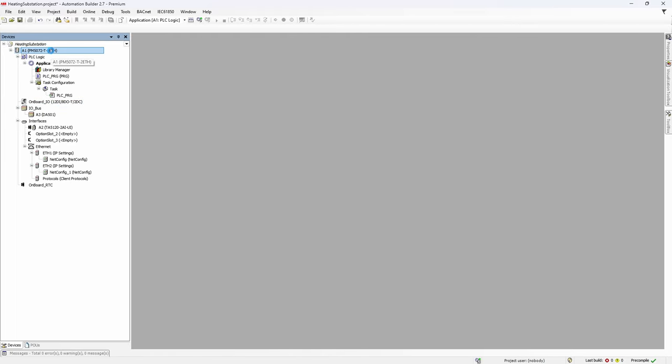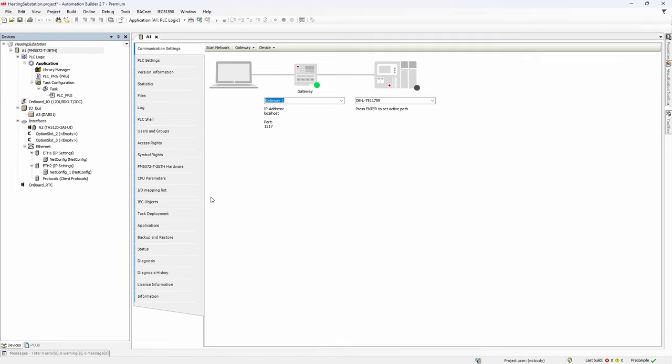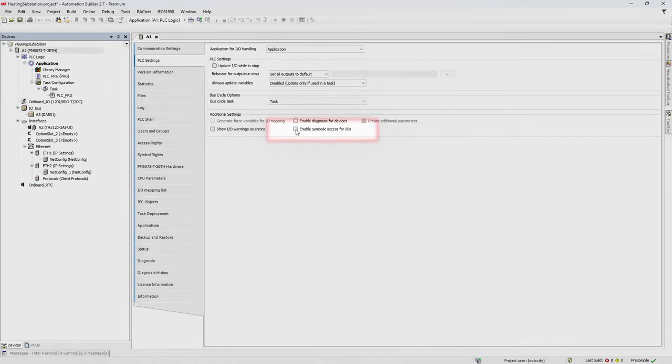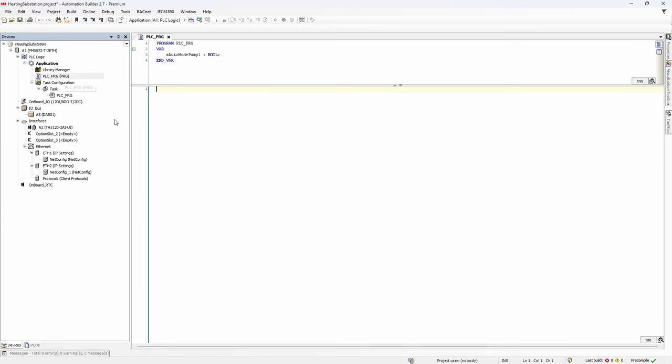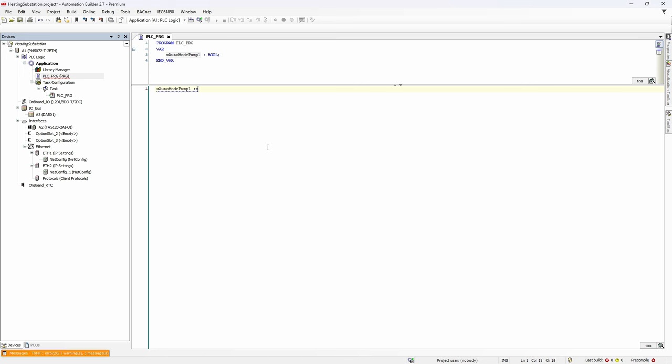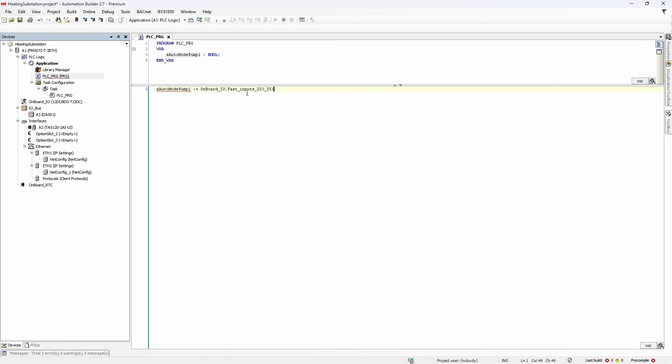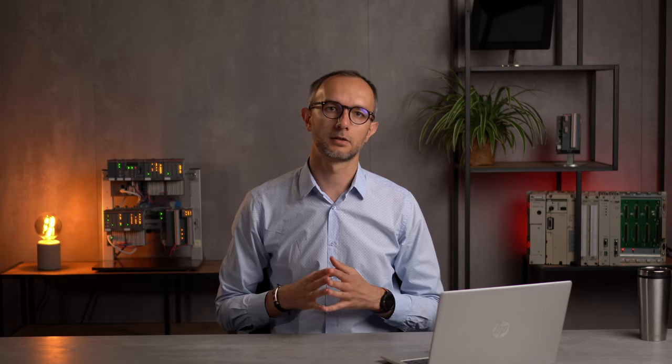The third way of IO mapping would require some settings change. We double click on CPU object in the hardware tree, then go to PLC settings, check enable symbolic access for IOs, and then press yes. And now if we go to code section, we can access embedded IO channels by typing the name of the module. onboard_IO dot and Automation Builder will show the list of variable sub elements of the module. We select fast inputs di0 di3 and since it's a byte variable we need to access bit 0 of this byte to get the value of digital input 0. This type of mapping is usually used in bigger projects where you have separate part of the control application which handles IO forcing, simulation, filtering, etc. Sometimes it's called IO isolation layer.